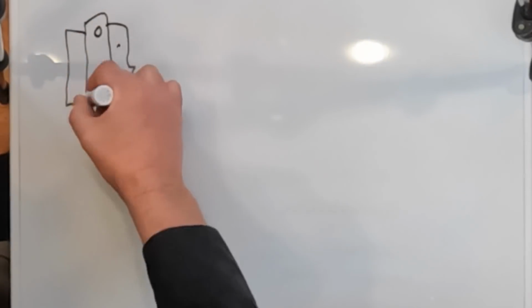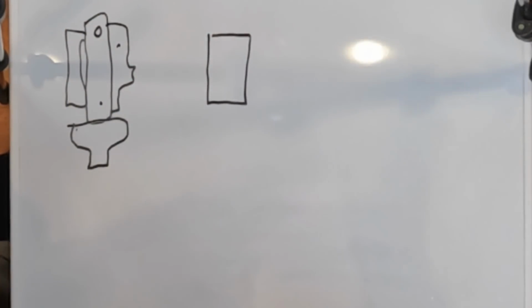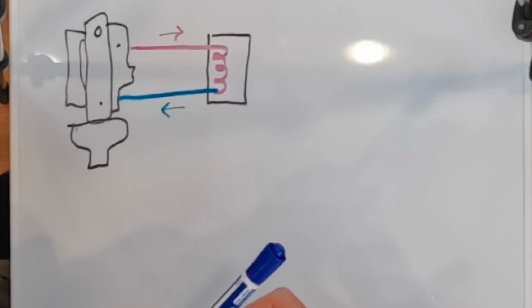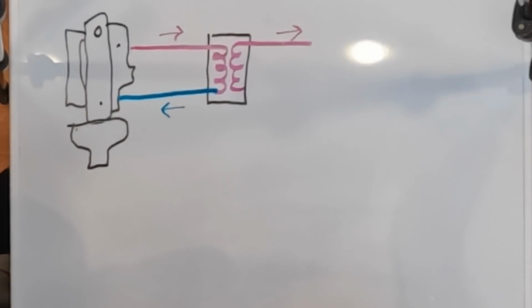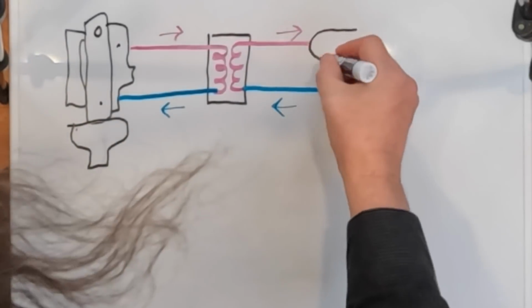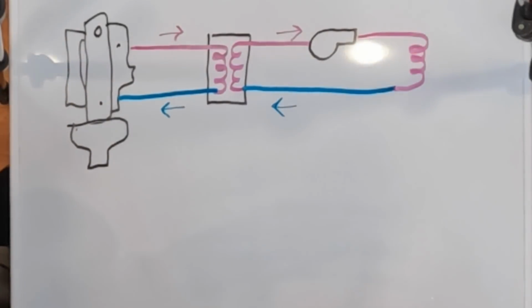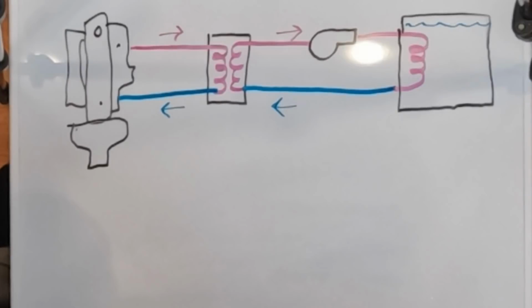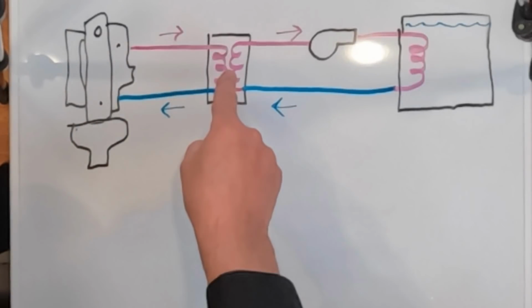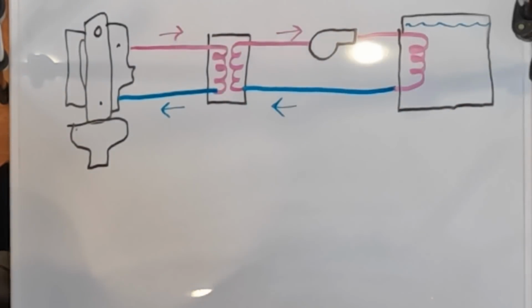I wanted to draw you a quick schematic of this heating system since we didn't get into the space heating part. We have the engine and the heat exchanger. Hot water comes out of the engine, cycles through the heat exchanger, and returns cooler. Out of the heat exchanger we have another circuit, the primary loop, which leaves hot and returns cooler, fed by a pump to circulate the water. That water is primarily circulated through the hot water tank and heats it. So we loop hot water from the engine which heats the heat exchanger, and we loop water around the primary loop from the heat exchanger, which heats the hot water tank.